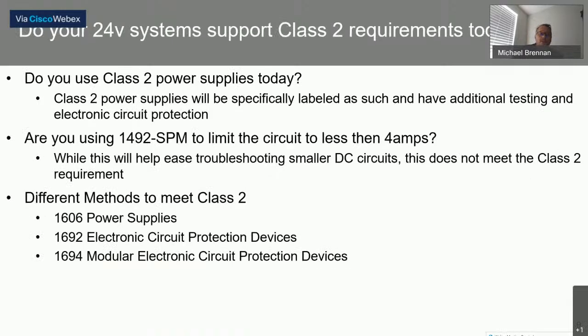So what do we see? I want to ask the question, do you use Class 2 power supplies today? Do you know if you do? They would be labeled as such, and just remember there's additional testing and circuit protection being done. Are you using 1492 SPM supplemental protectors to limit the circuit to less than 4 amps? What I've seen a lot over the years is that folks know they need to limit and use a Class 2 circuit, but they'll use a supplemental protector to do that because previously there really wasn't a very easy method to do this.